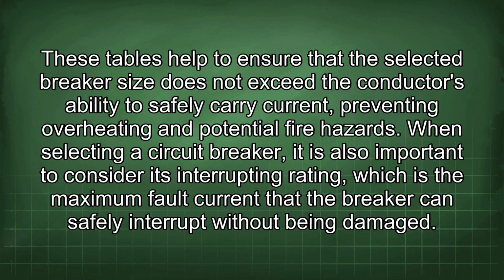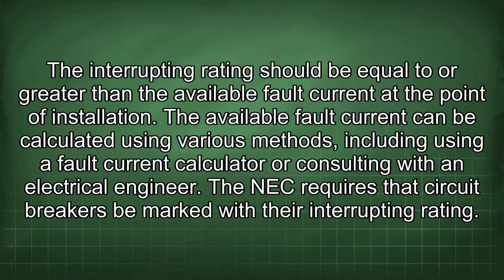These tables help to ensure that the selected breaker size does not exceed the conductor's ability to safely carry current, preventing overheating and potential fire hazards. When selecting a circuit breaker, it is also important to consider its interrupting rating, which is the maximum fault current that the breaker can safely interrupt without being damaged. The interrupting rating should be equal to or greater than the available fault current at the point of installation.